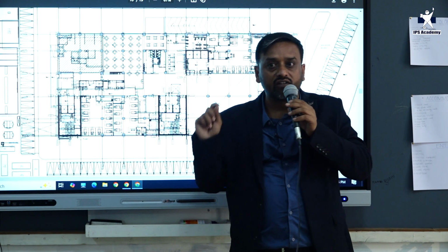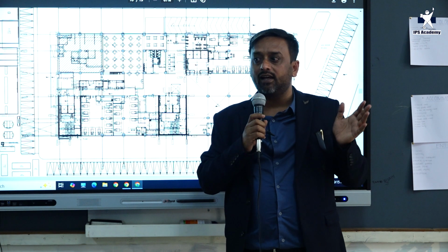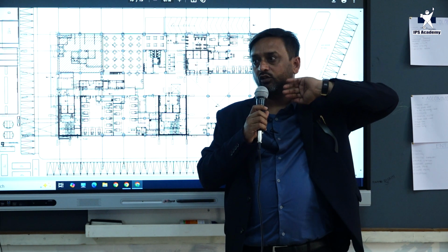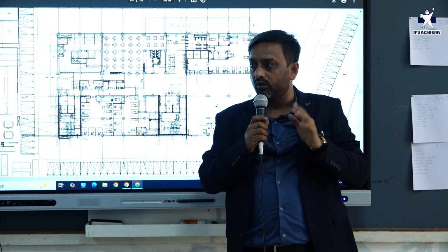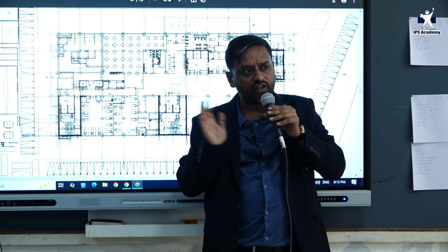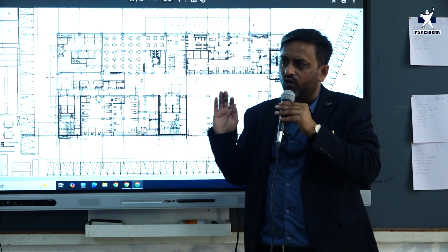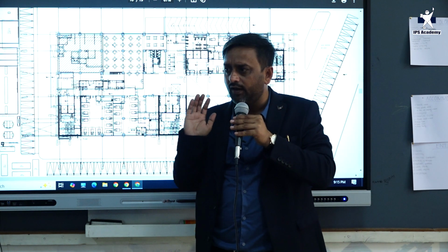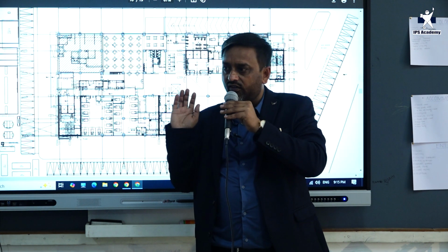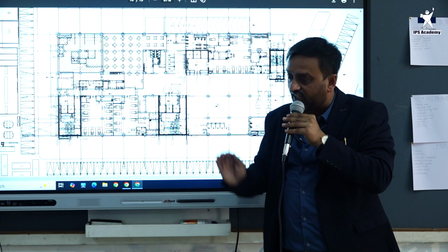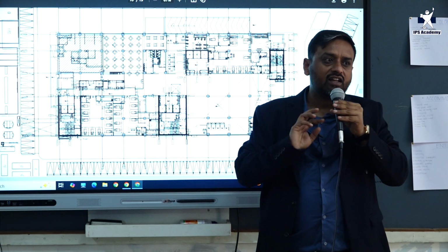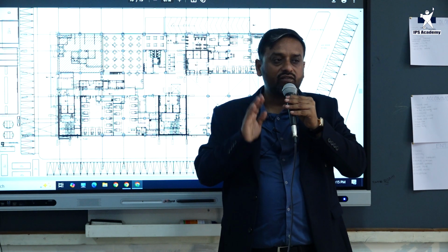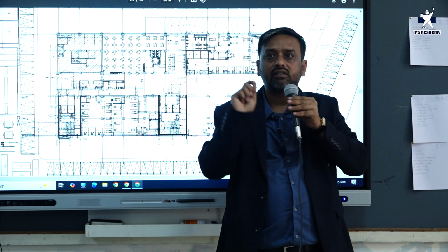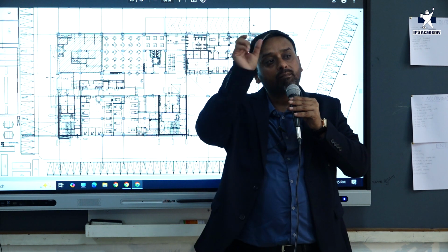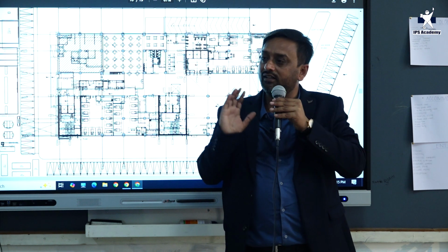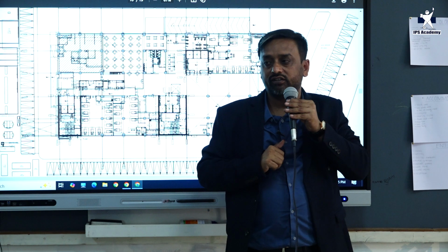UPS dedicated to server are separate. So these are zoned. Above OT we have kept the UPS for the OT, like 7 to 8 UPSs of 10 kVA for each OT. Load was very less, but we thought of having 10 kVA, 3 phase in, 3 phase out for the OT. Same way server. Server also we need separate dedicated. Their earthings are also dedicated. You cannot mix the earthing to the building earthings. So same way server is having different UPS, OT is having different UPS, and the complete building power backup is catered by 180 kVA of UPS.